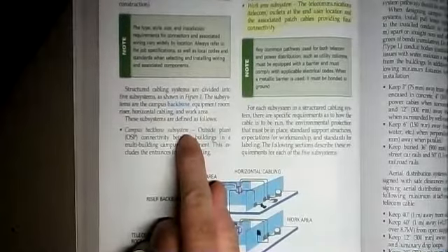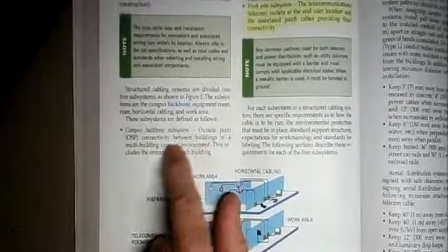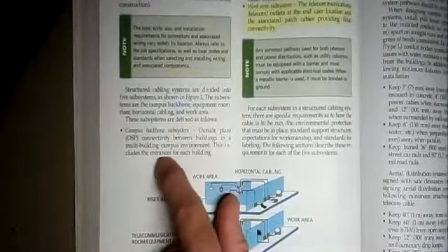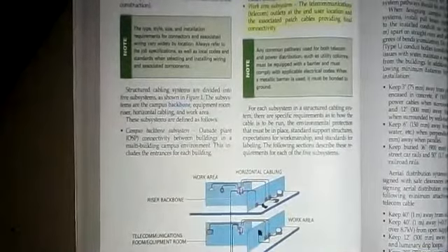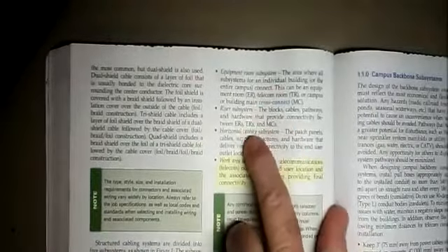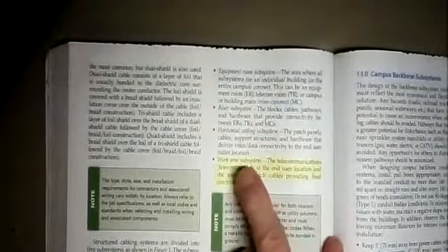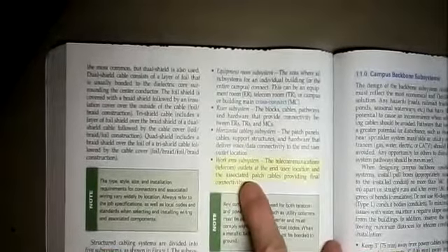And here they are. It has the campus backbone system, outside plant connectivity between buildings in a multi-building campus environment. This includes the entrance for each building. And then you go up to the equipment room subsystem, the riser subsystem, the horizontal cabling subsystem, and then the work area subsystem. This is the last, like the branch circuit that goes to your desk. The telecommunications outlets at the end user location and the associated patch cables providing final connectivity. So when you plug in to an Ethernet jack at your desk and plug it into your computer, that is the work area subsystem.